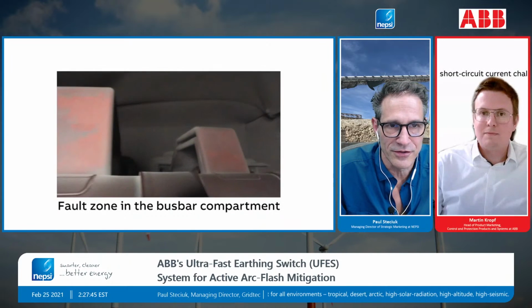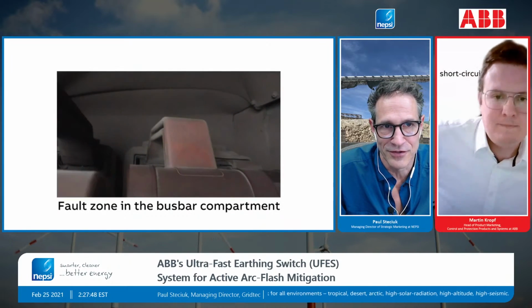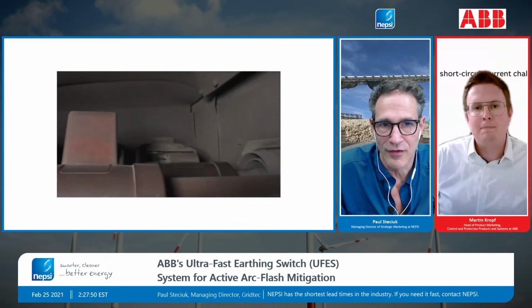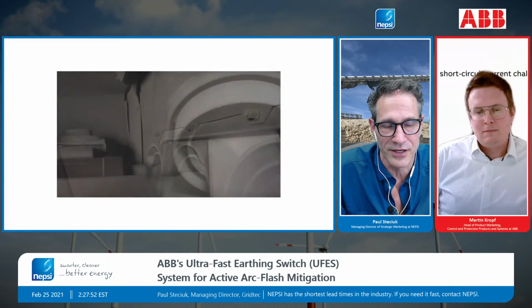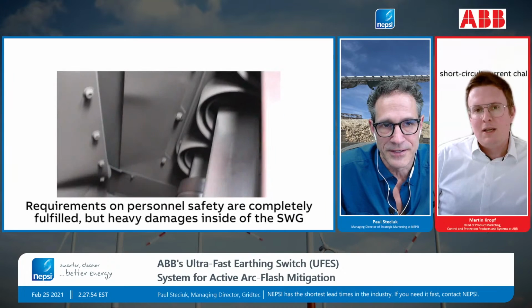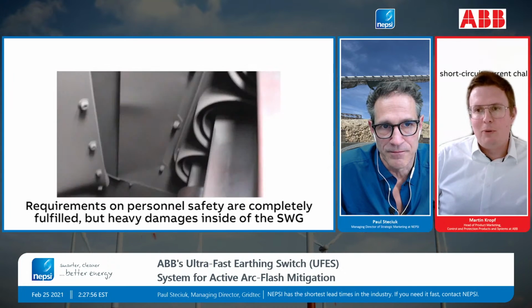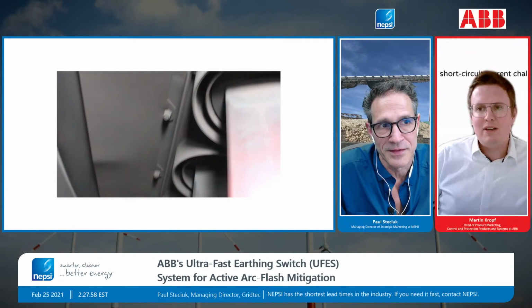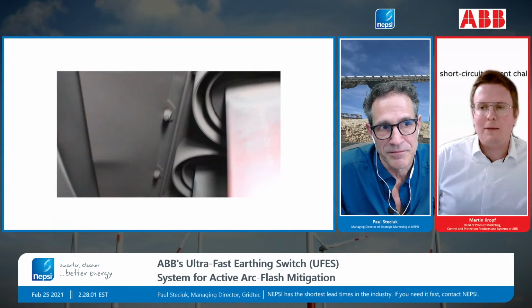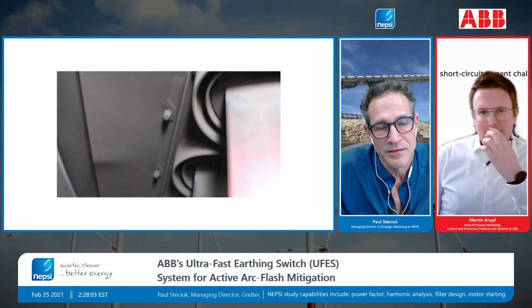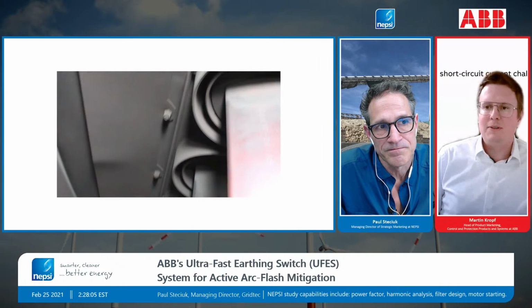This is that switchgear without UFES, and you can see a lot of damage to the equipment. It would no doubt need replacement. But we have to say the test would have been passed - an internal arc, a passive internal arc test, would have been passed with this.